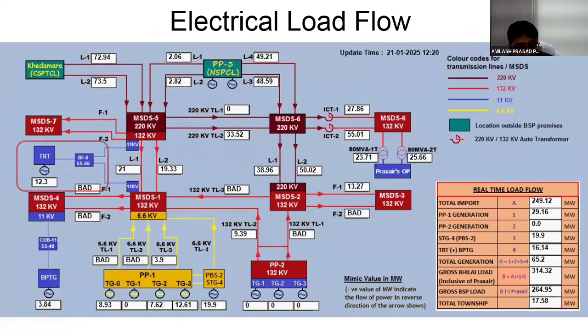Now coming to the TRT. TRT generation is 14 megawatt, and BPTG is 4 megawatt. In the TRT, we use the kinetic energy of the blast furnace gases to rotate the turbine, and we generate 14 megawatt of power. These are all connected through the step-up transformer of 11 to 132 kV through our various substations of MSDS.